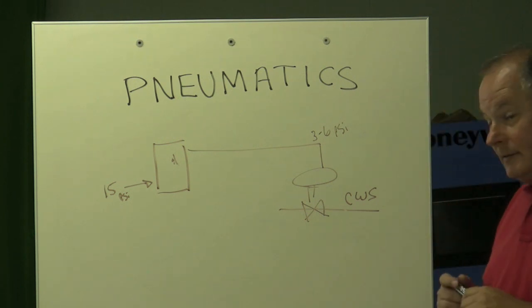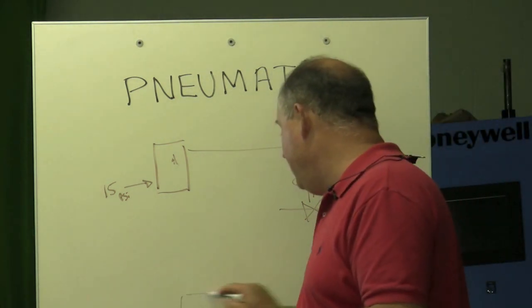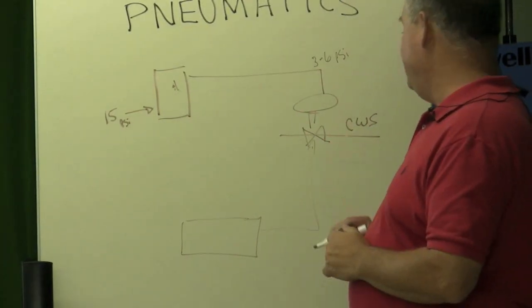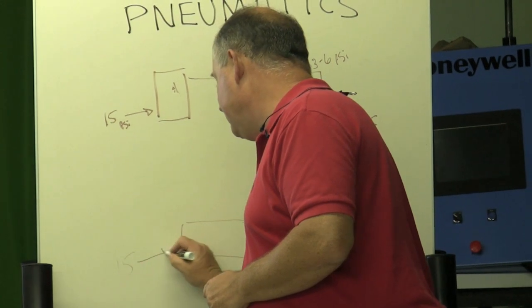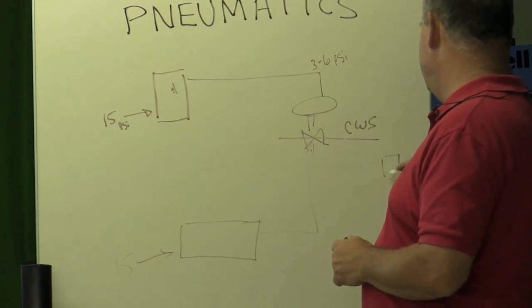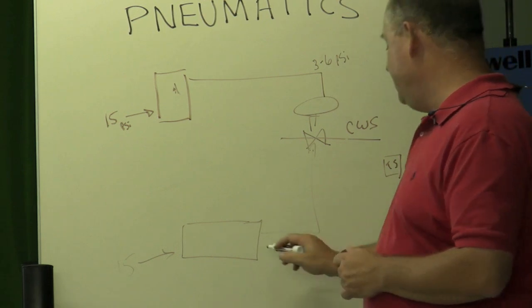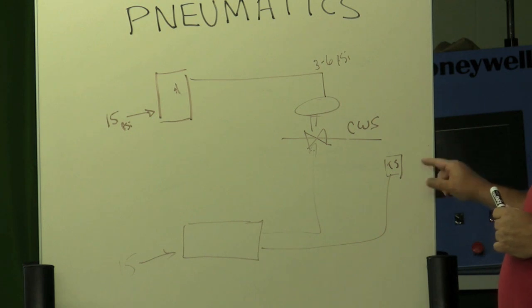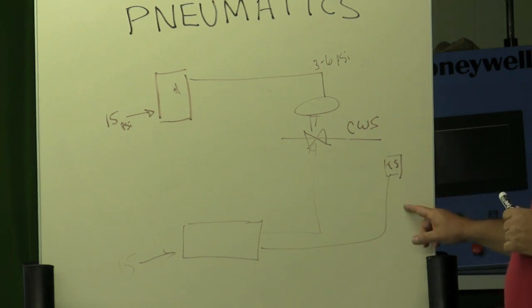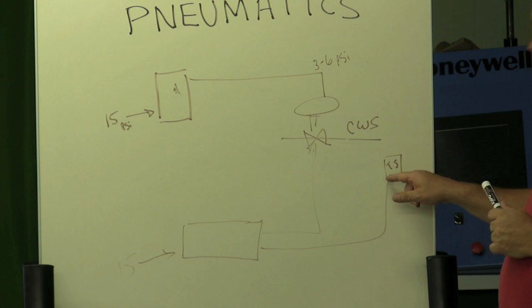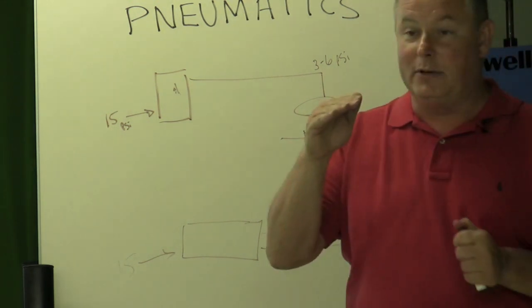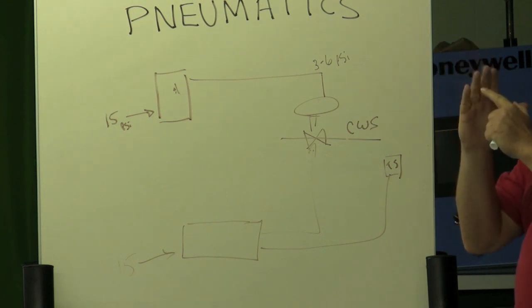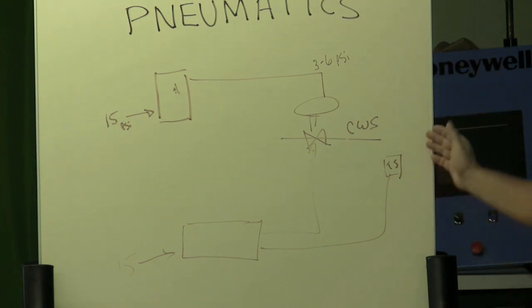Now, another way we could do this, if we had a receiver controller, we'd have an output that goes to that valve, we'd have 15 PSI coming into it, and somehow over here we'd want a little temperature sensor that's in the space, and it would run over. The temperature sensor that's in the space would be a one-pipe device.